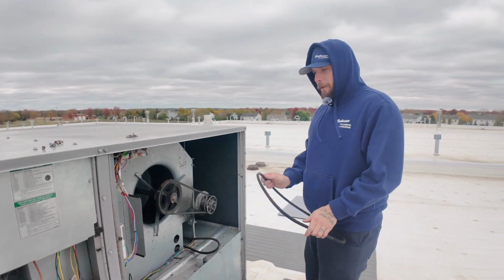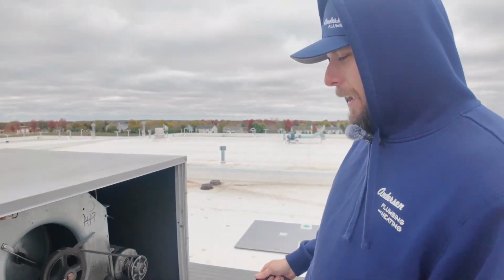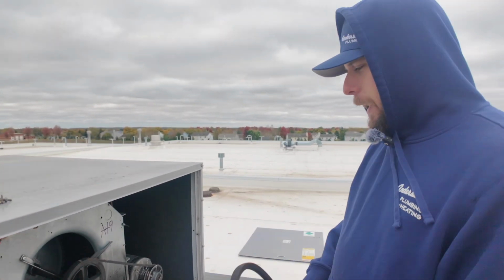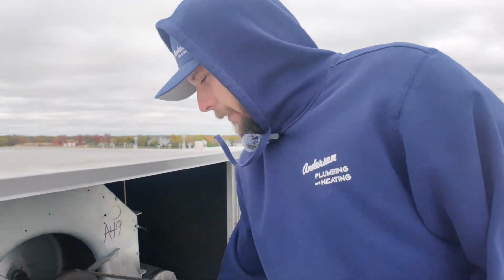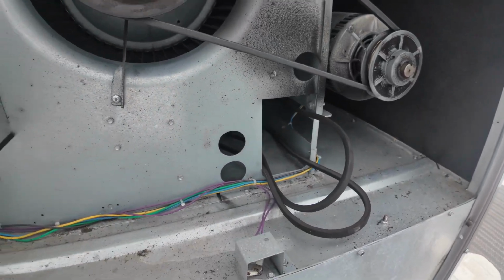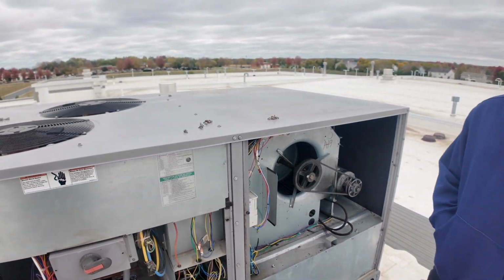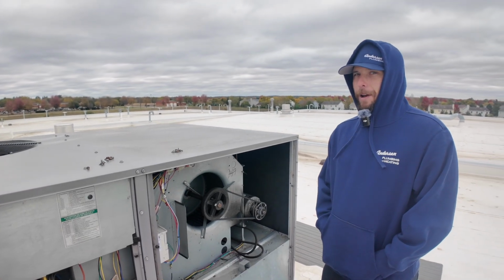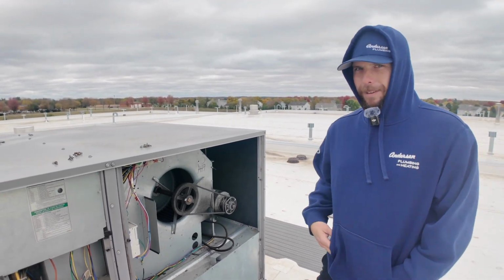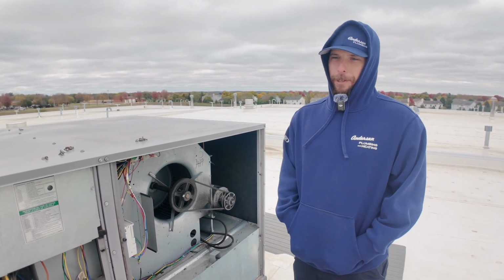It is kind of funny though, whenever you open these units up, if you have a belt that's not broken, that's usually where you find it. Now, why do we leave all the old parts inside the unit? Well, because at 2 o'clock in the morning when you need to fix it and you don't have a belt in your truck, you're saving the next technician. They can at least get through the service call.